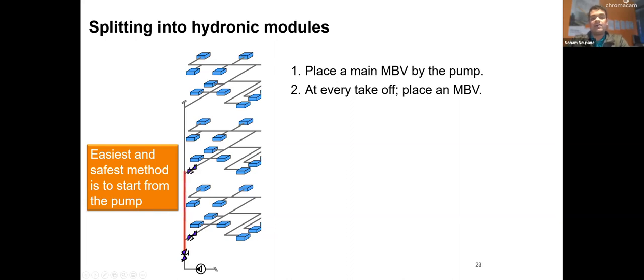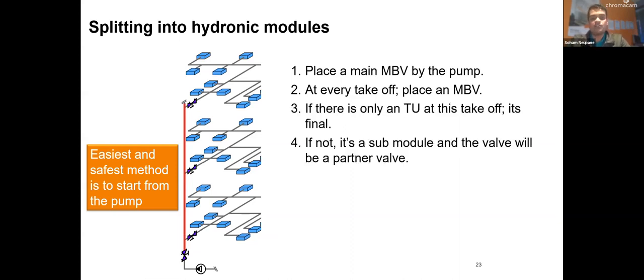So we do that again. At the takeoff, you place a manual balancing valve. One thing to note is that if there's only one terminal unit at any of those takeoffs, just know that that's not your partner valve, that's just your manual balancing valve. We don't need any more manual balancing valves there. But if there's more than one terminal unit, then it's a sub-module. So what we're doing right now, where we place this valve, because there's more than one terminal unit, that is now a module. So this is now a partner valve, and we know that we need to go into these sub-modules and start placing manual balancing valves in there, okay?